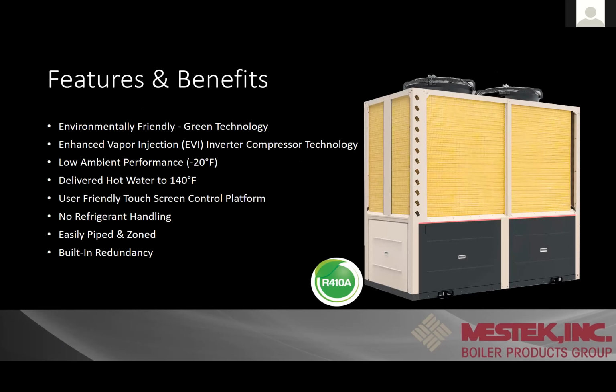So, benefits. It's environmentally friendly, like we're talking about, green technology. There's the enhanced vapor injection EVI inverter compressor. I won't get too crazy, but it's a cold climate heat pump. It has a third small internal plate heat exchanger called an economizer. Within that refrigerant cycle, they're utilizing a bypass valve that takes the refrigerant vapor from that economizer, so it's a warmer refrigerant, and injects it into the head of the compressor. So it's matching that colder refrigerant with this warmer refrigerant, giving us higher pressures and the ability to get low temp heating out of it. What this EVI does is it increases the heating capacity by about 20% over a standard compressor.